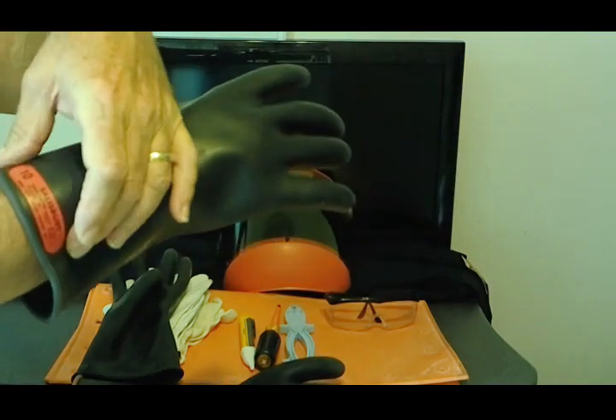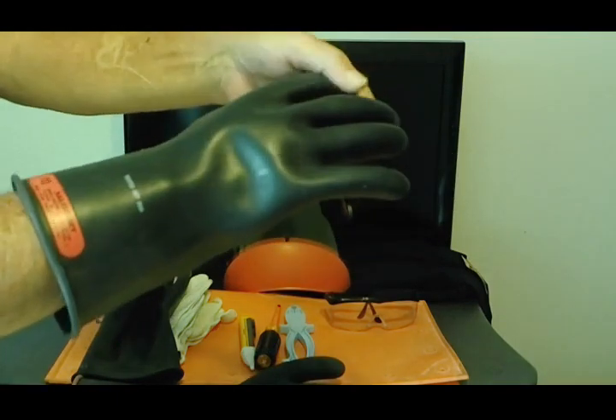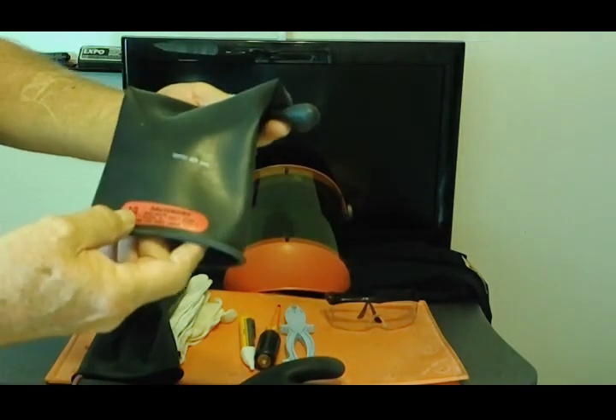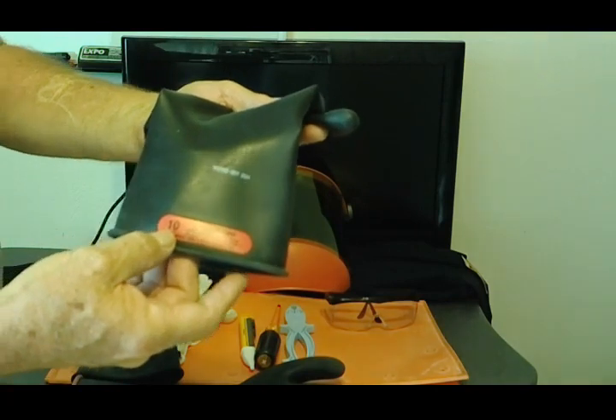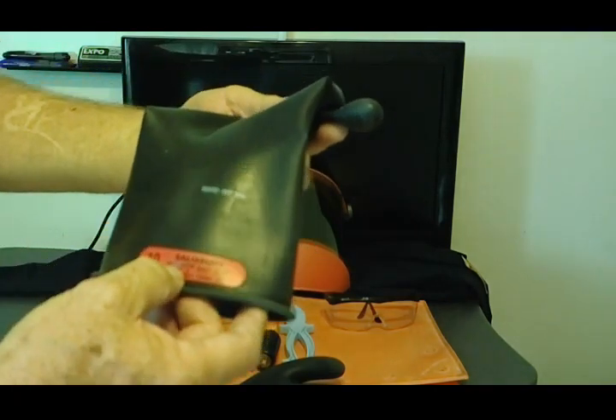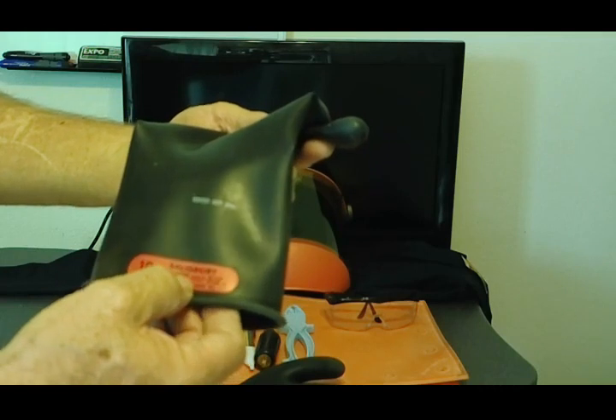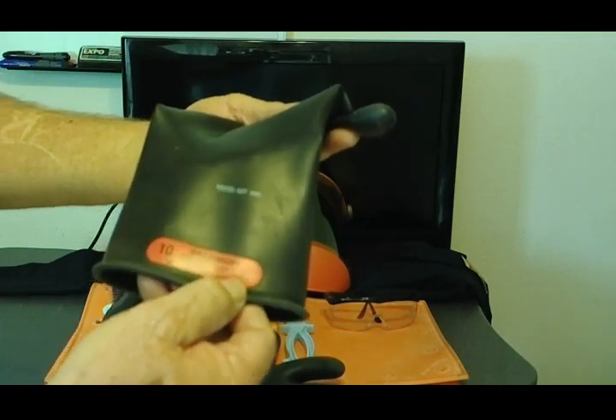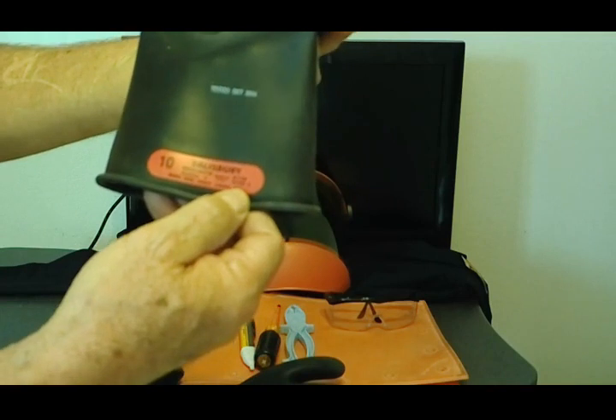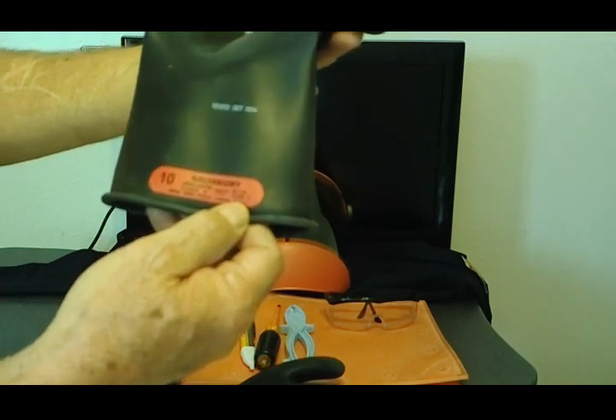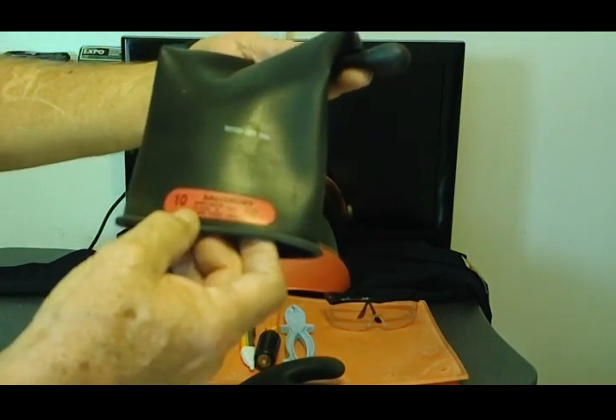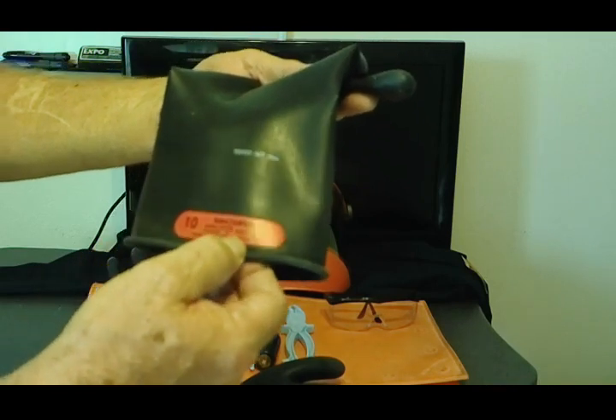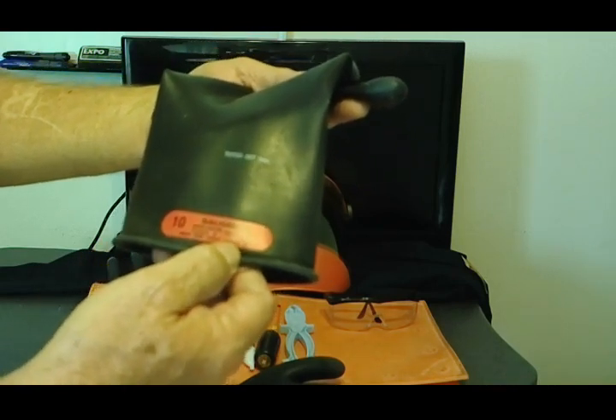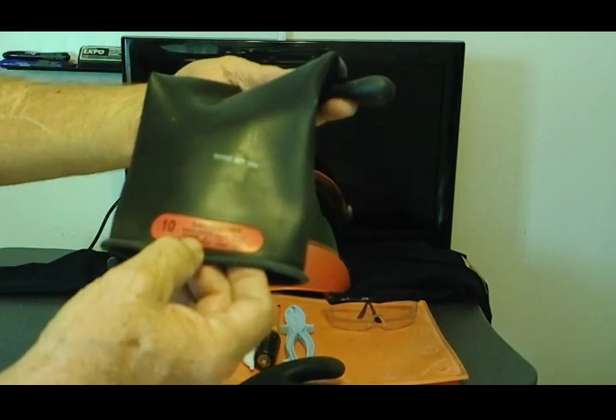The electrical gloves are going to have an identifier of what they're rated and how they're used. Right here on this tag, tags are color coded as to class of gloves. This is a size 10 glove. It is made to ANSI and ASTM standards. It is a type 1 glove, which is natural rubber. Type 2 is synthetic rubber. There are people allergic to rubber. Maximum use is going to be 1,000 volts AC power. This is a class 0 glove.